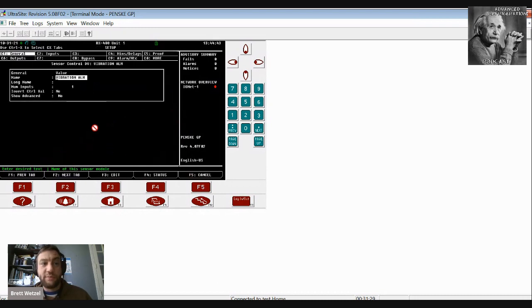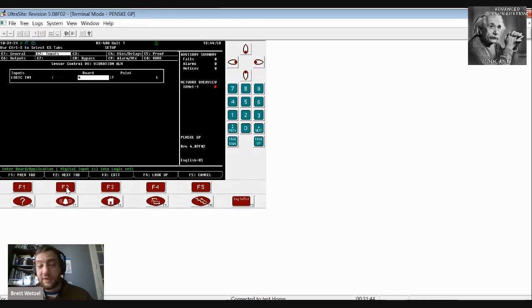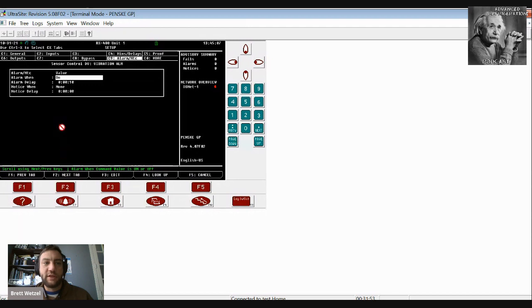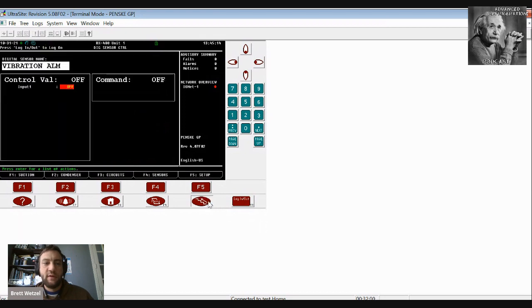Now, this particular device is on an evaporative condenser. And basically, if the bearings go bad or the big fan blade breaks on the evaporative condenser, it basically will tell you that you have a problem hopefully before something massive breaks, right? And then if we go over to alarms, basically alarms, if it's on for more than 10 seconds, then it'll kick on.